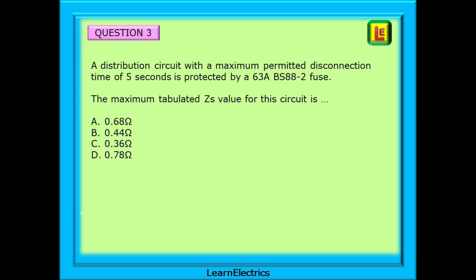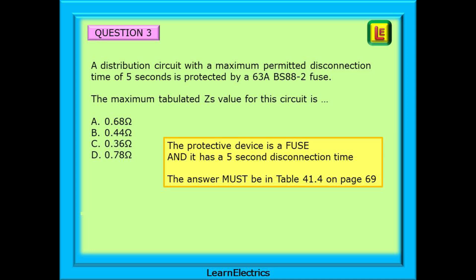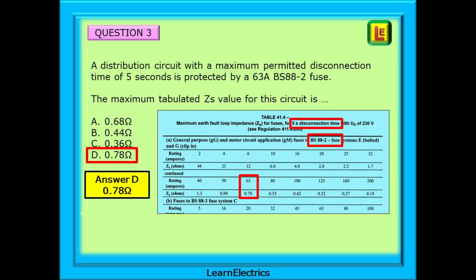Another question on ZS values. A distribution circuit with a maximum permitted disconnection time of 5 seconds is protected by a 63 amp BS 88-2 fuse. The maximum tabulated ZS value for this circuit is what? The protective device is a fuse and it has a 5 second disconnection time — all given in the question. So the answer must be in Table 41.4 on page 69. Find the correct section for BS 88-2 fuses, find 63 amps in the range, and read off the ZS value. Our choice should be answer D — 0.78 ohms.